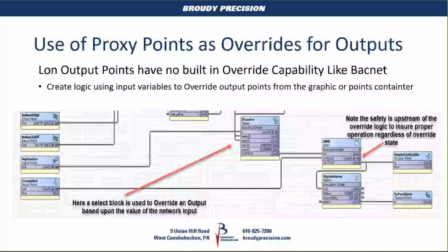Overrides can get you in trouble—if you give end users overrides, a lot of times they won't manipulate a set point, they'll just go right to an override. So overrides get us in trouble because it basically takes us out of automatic operation. But they're extremely useful when you're doing commissioning and testing and some other things that might be required.